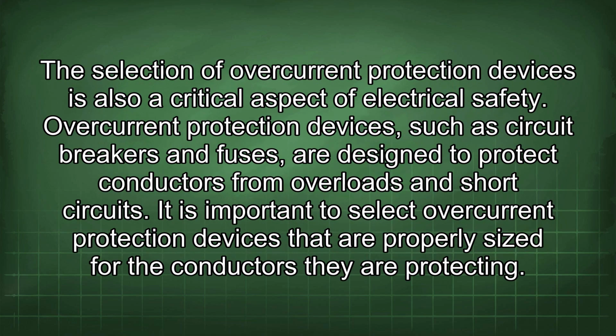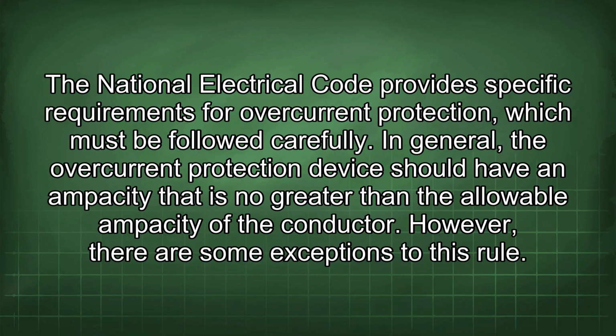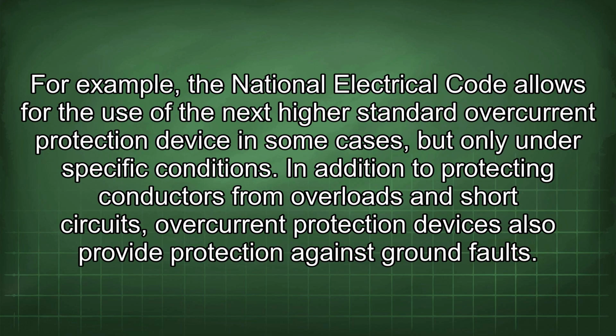The selection of overcurrent protection devices is also a critical aspect of electrical safety. Overcurrent protection devices, such as circuit breakers and fuses, are designed to protect conductors from overloads and short circuits. It is important to select overcurrent protection devices that are properly sized for the conductors they are protecting. The National Electrical Code provides specific requirements for overcurrent protection, which must be followed carefully. In general, the overcurrent protection device should have an ampacity that is no greater than the allowable ampacity of the conductor. However, there are some exceptions to this rule. For example, the National Electrical Code allows for the use of the next higher standard overcurrent protection device in some cases, but only under specific conditions.